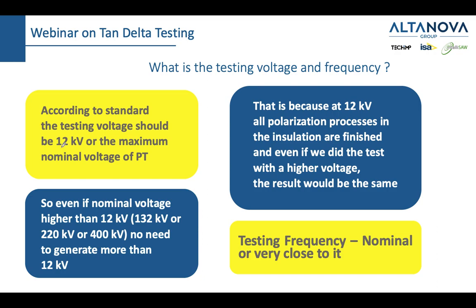Also, what is the testing frequency? The testing frequency should be as close as possible to nominal, so 60 hertz or 50 hertz. Now, there are some differences when it comes to measurement voltage and frequency, and that mostly concerns rotary machines, so mostly generators. Generators can sometimes be tested with up to 15 kilovolts, if necessary, and in that case you might change the frequency a little bit more. In the case of transformers, you shouldn't change the frequency more than, let's say, 2 hertz. So this is about frequency and about voltage.